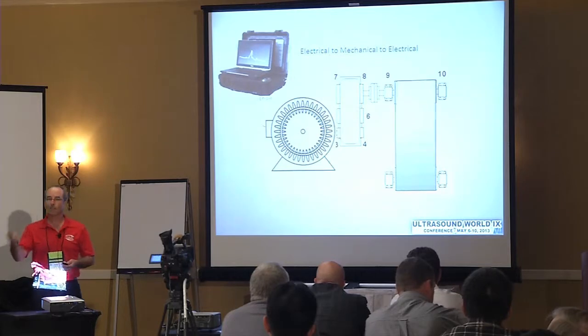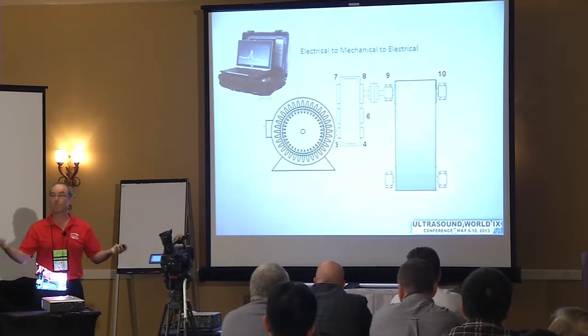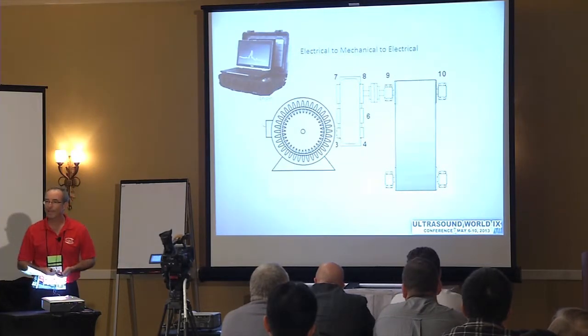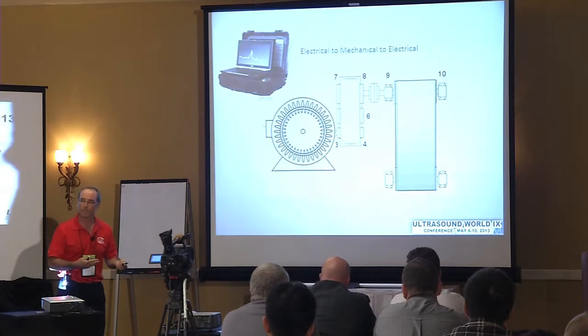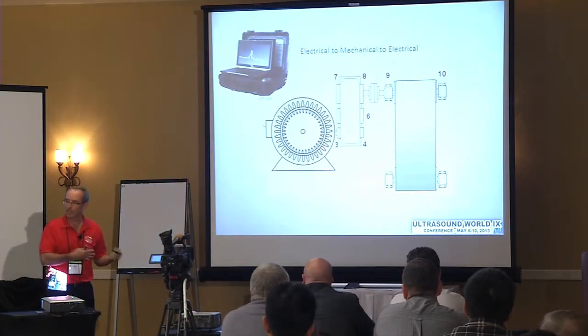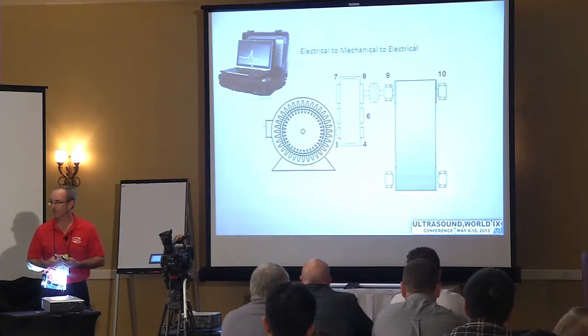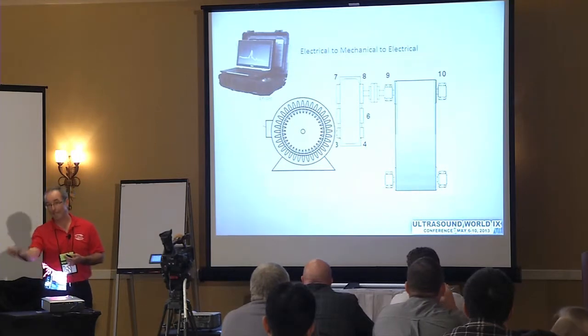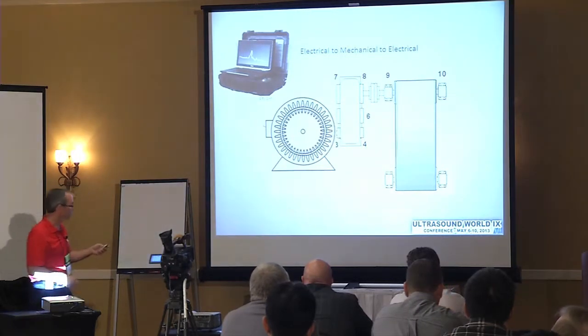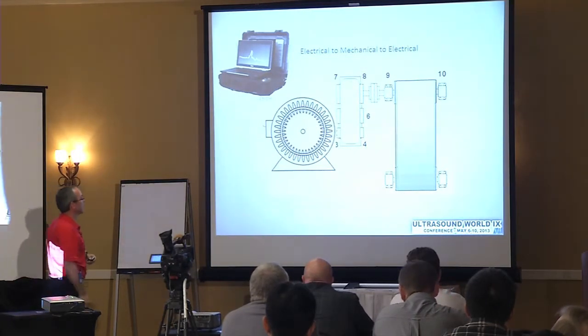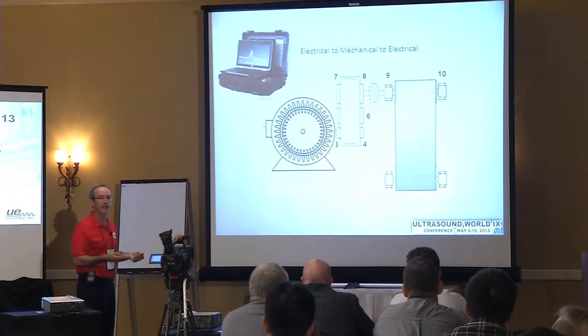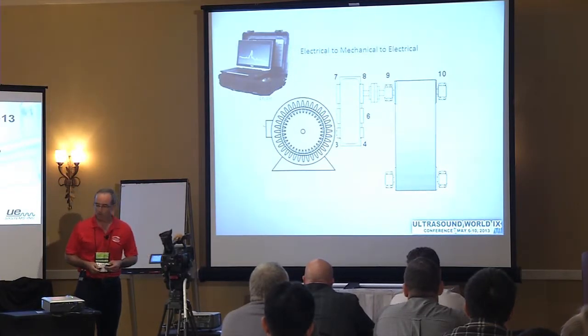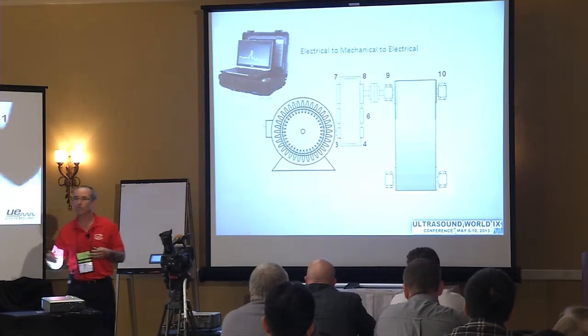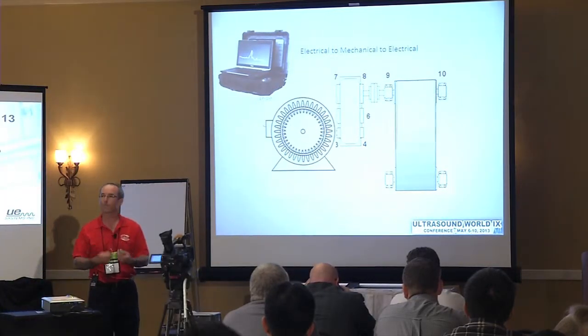Every one of your motors in your plant is hooked to some type of application, sitting there waiting to be taken advantage of. Whether you're testing electrical, vibration, or ultrasonics, a lot of times you can go to the motor and see a lot of things happening, both mechanically and electrically. So here's a bit of animation to give you a taste of what's available out there—a hidden sensor is the goal.